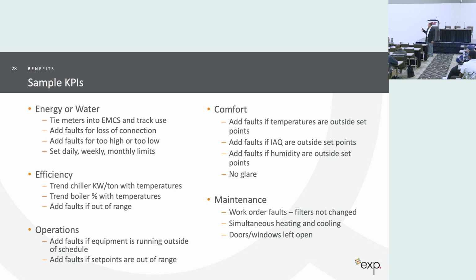These are some defined KPIs. So these are things that we do within our buildings. And I'll go into them, like energy and water. You can tie your meters into the system and track use. And so you can add a fault to say, I lost that meter. A lot of times we'll go to buildings and this meter had stopped communicating, and nobody knew about it. So set up a fault.